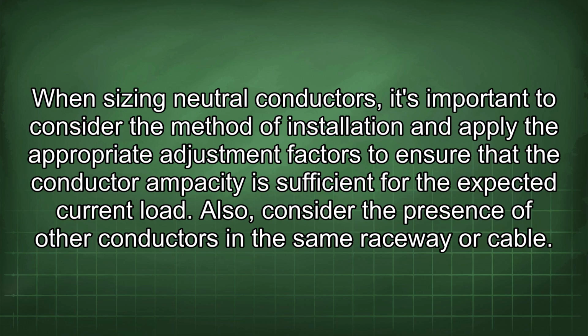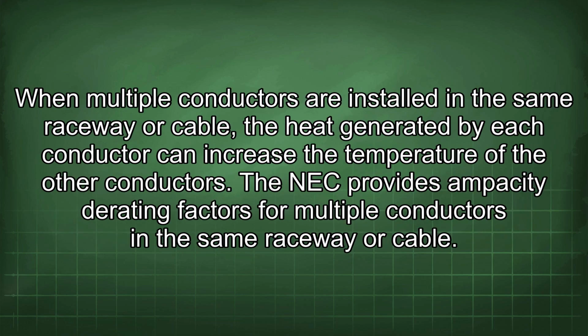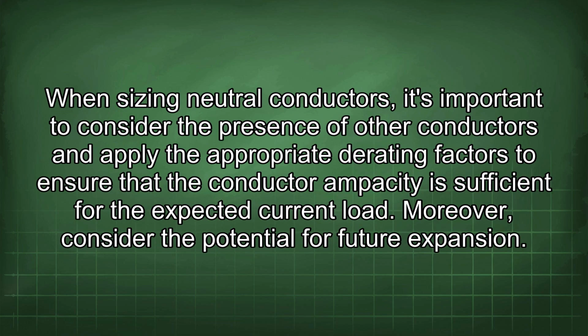Also, consider the presence of other conductors in the same raceway or cable. When multiple conductors are installed in the same raceway or cable, the heat generated by each conductor can increase the temperature of the other conductors. The NEC provides ampacity derating factors for multiple conductors in the same raceway or cable. When sizing neutral conductors, it's important to consider the presence of other conductors and apply the appropriate derating factors to ensure that the conductor ampacity is sufficient for the expected current load.